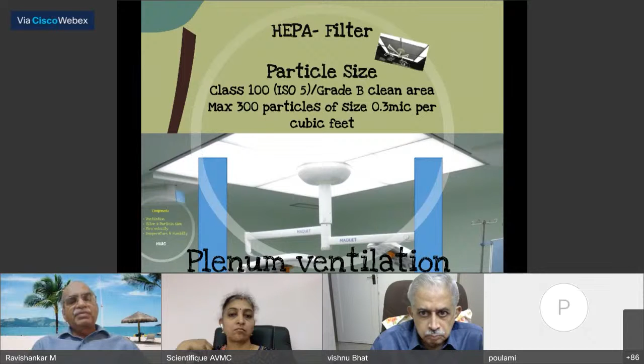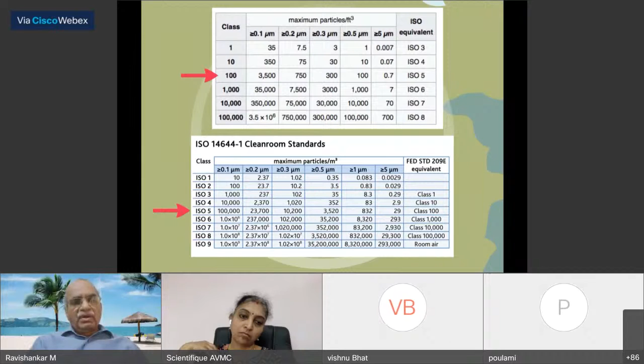Here, when you talk about class, it is about particles per cubic feet, whereas when you talk about ISO, it is per cubic meter. So the number of values will be the multiplication by the conversion of feet into cubic meters. Class 1 is the minimal, and class 100 is recommended for the operation theaters. Class 1000 is recommended for the corridors and other places, and class 10,000 is recommended for other places in the hospital. Similarly, ISO 5, 6, 7 are recommended for the hospital.